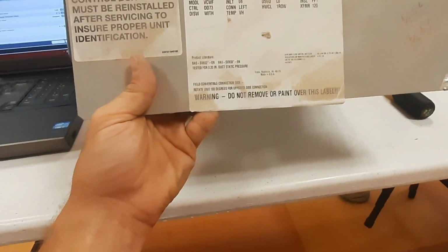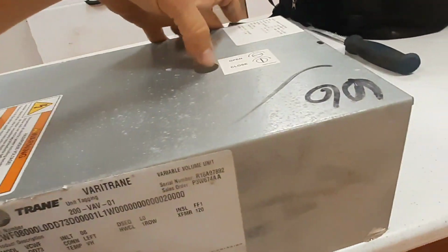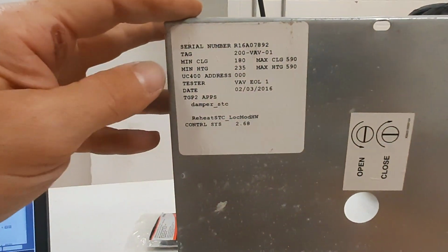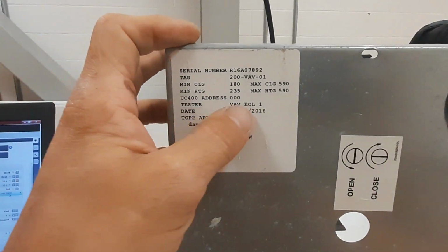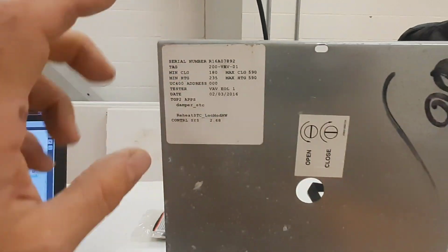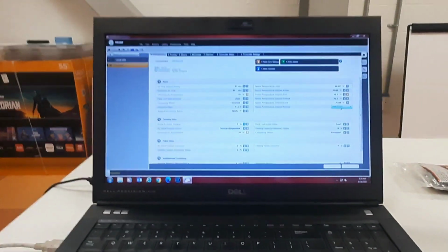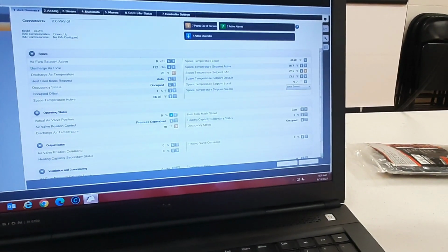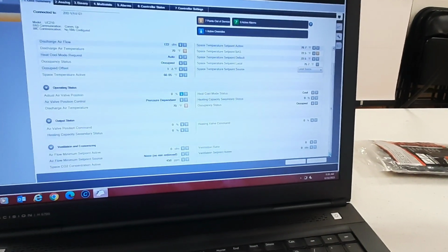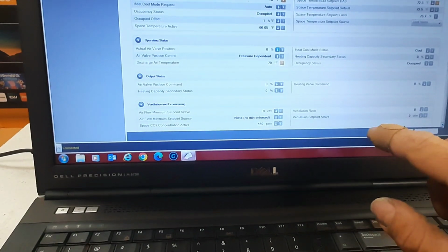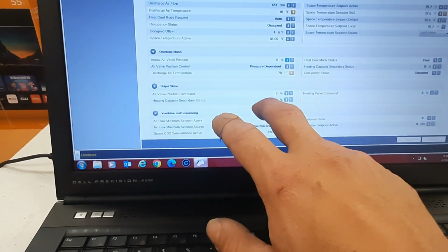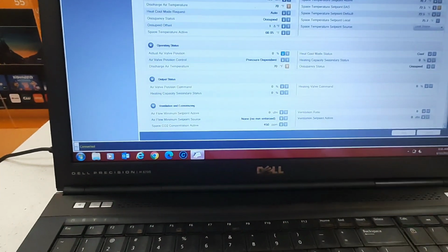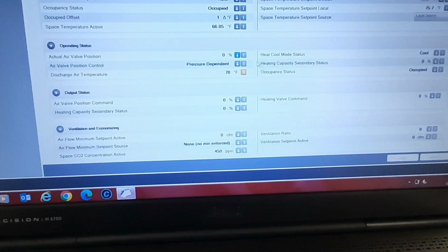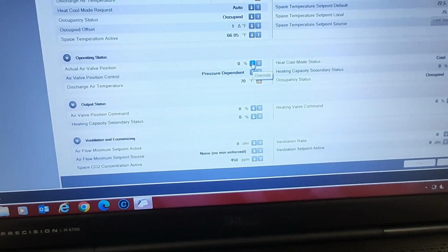Let's go test everything out. We can see this is all our information here, and then typically you'll have min heating and cooling, max heating and cooling. Those are starting points for the position or the min-max settings on airflow. So we'll have to go down and set all of our min-max. It's in cooling mode. This is my override here. This must have been how I overrode it initially, because we can see it's override the air valve position at 0.